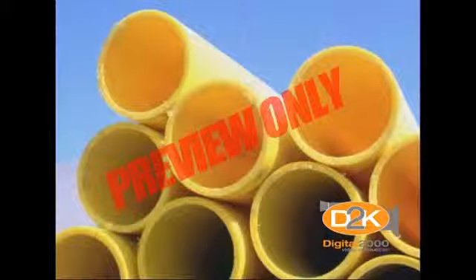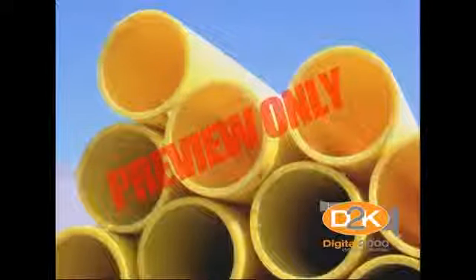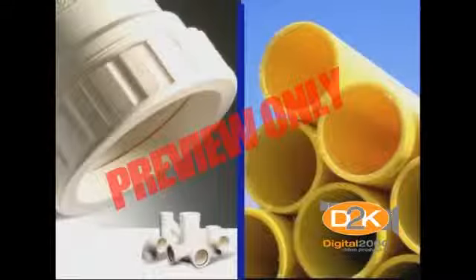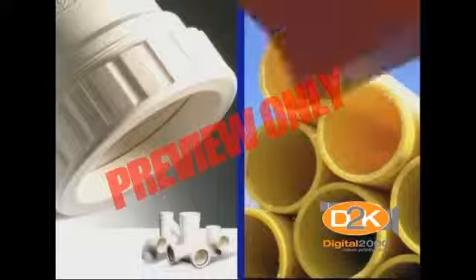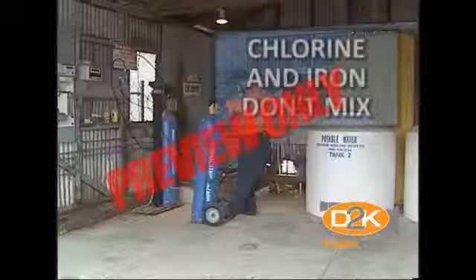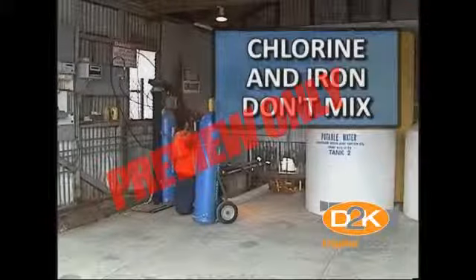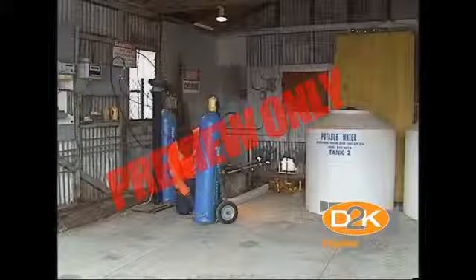Plastic pipe does not have sufficient strength and must not ever be used for any portion of a high-pressure gas system. Doing so could lead to a fracture of the line and lead to all sorts of hazards, including flying plastic shrapnel. Chlorine reacts with iron. Therefore, cast iron pipe must never be used for chlorine gas.